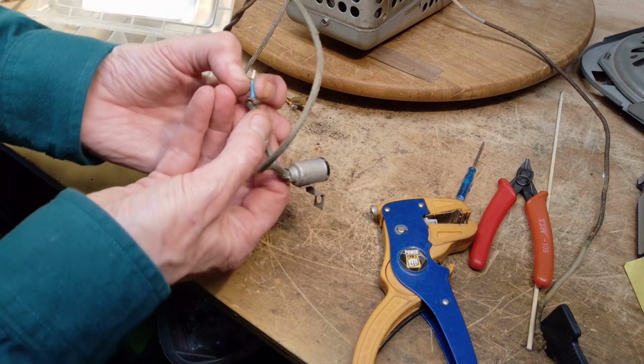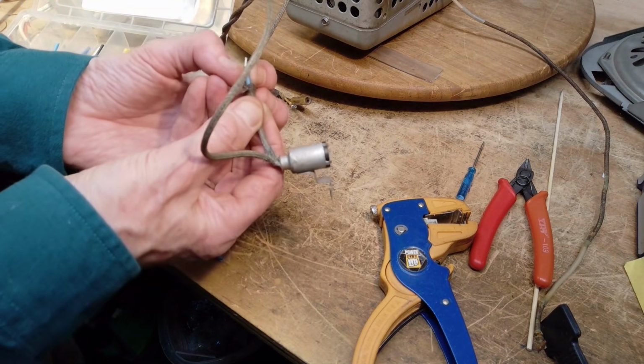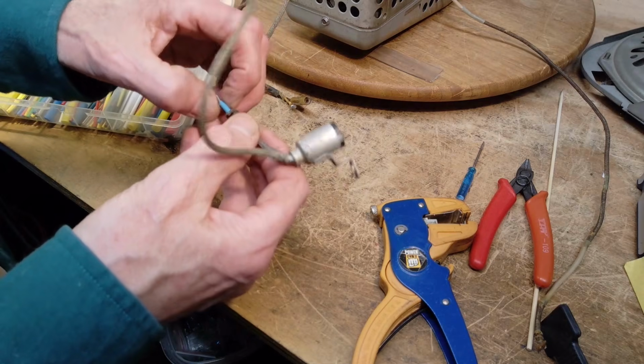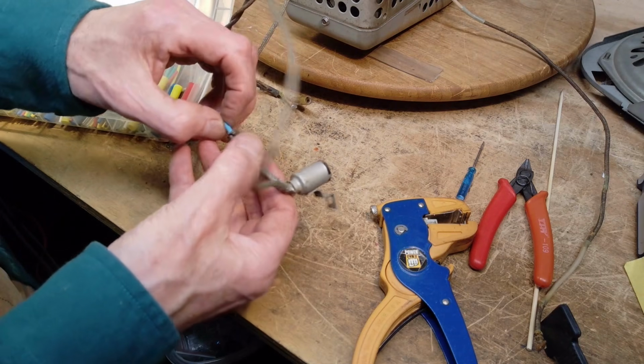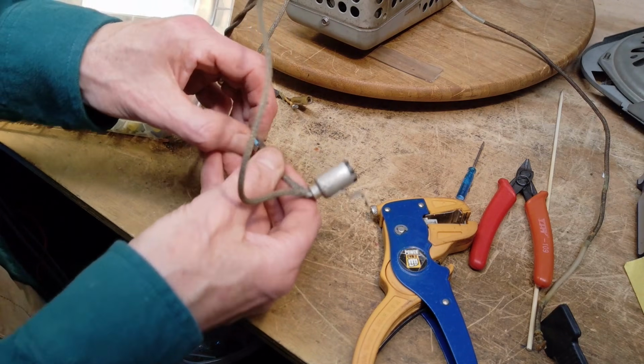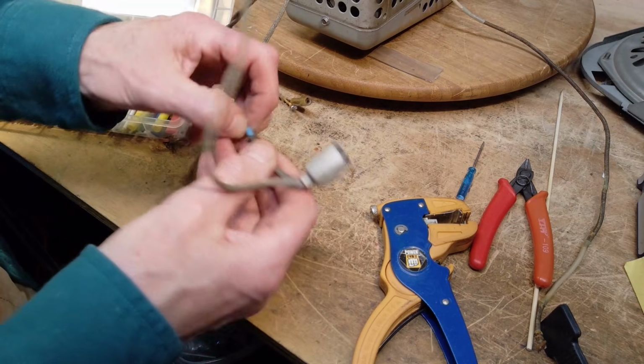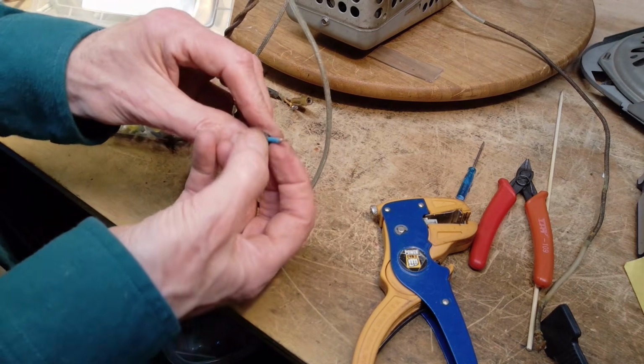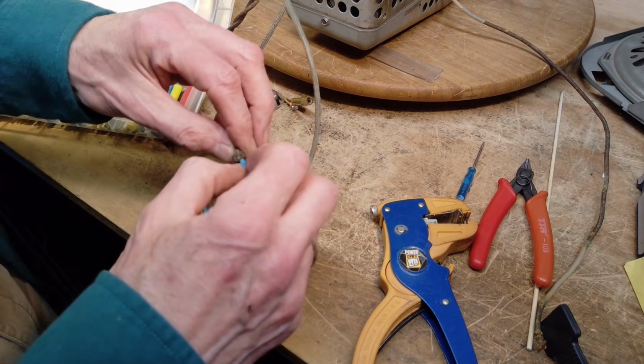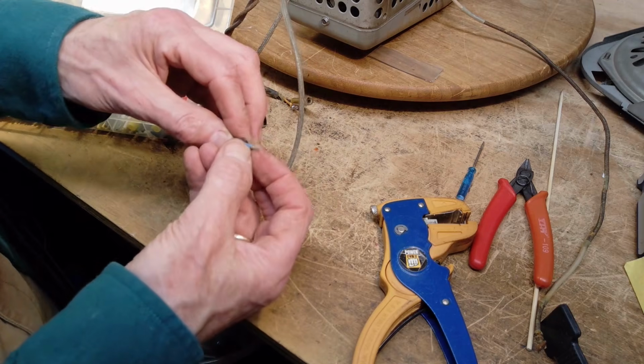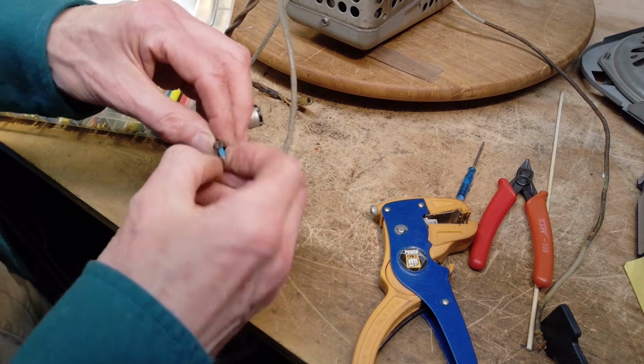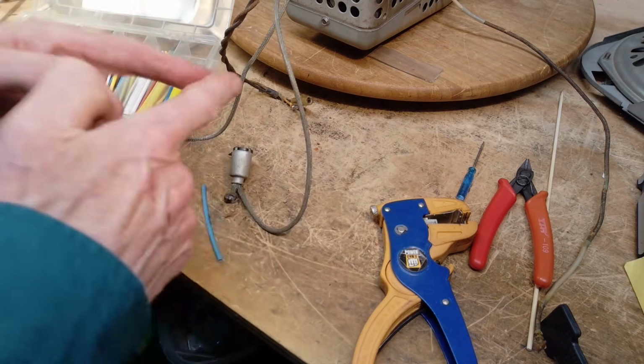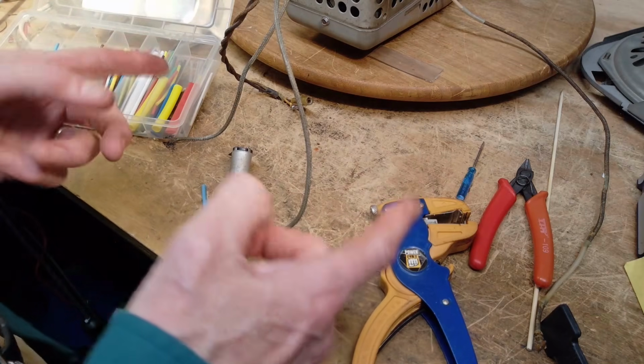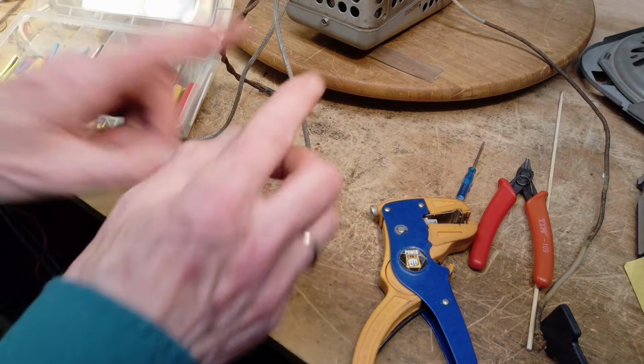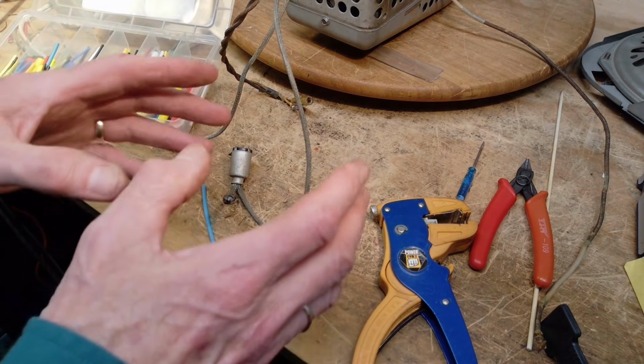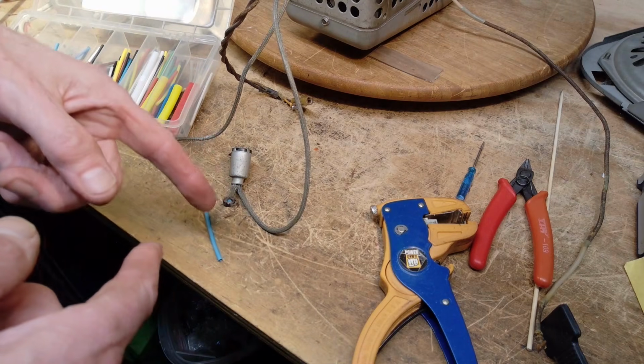Going back to my job years ago, when one of these cables failed, I'd become informed about it, and off I would go, get in a truck and drive out to the location. Often the crews were there already working, and sometimes they'd already pulled cable out of the ground, that defective cable. They pull it out between manholes. Everything is manhole to manhole. So you're not replacing a couple feet of cable, even though the fault is just a little tiny piece.